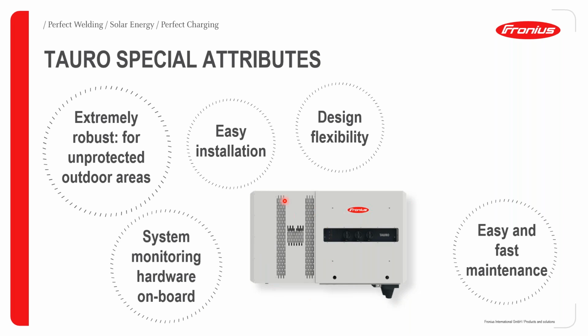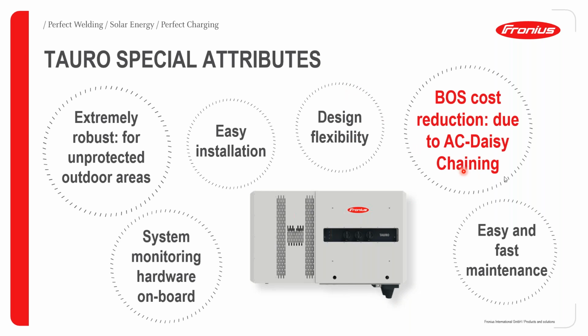The major difference also here is that the Fronius Tauro is utilizing the pilot. As you know, the SnapINverter series is using the data manager for communication, but the Fronius Tauro and the Gen 24 Plus inverters are utilizing something now that we call the pilot. That is already integrated as standard in the Fronius Tauro. And then, of course, the key highlight is the possibility of BOS, or balance of system cost reduction, due to the AC daisy chaining capability of the Tauro series of inverters.